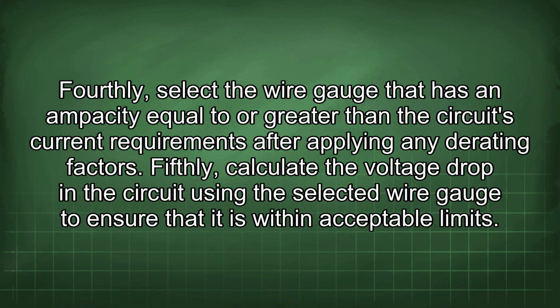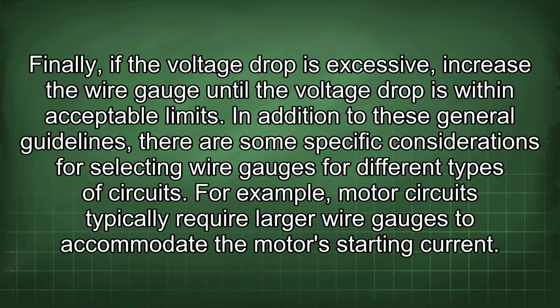Fourthly, select the wire gauge that has an ampacity equal to or greater than the circuit's current requirements after applying any derating factors. Fifthly, calculate the voltage drop in the circuit using the selected wire gauge to ensure that it is within acceptable limits. Finally, if the voltage drop is excessive, increase the wire gauge until the voltage drop is within acceptable limits.